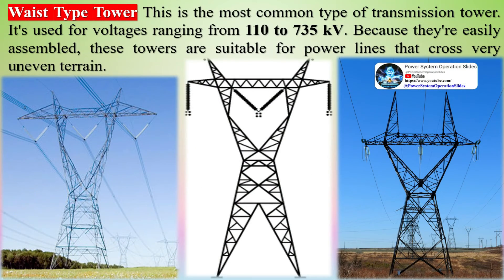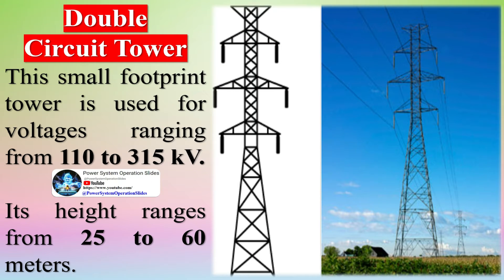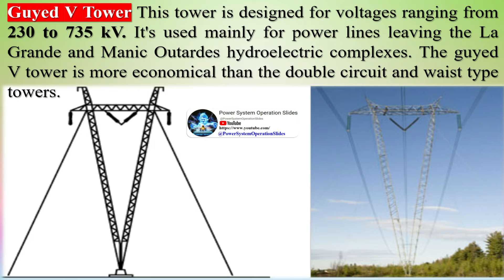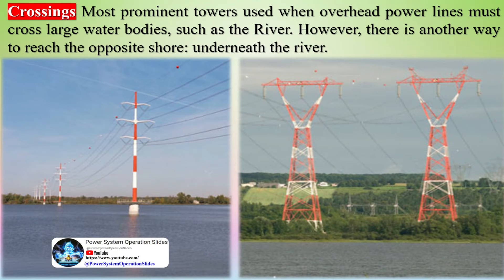The waist-type tower is the most common type of transmission tower, used for voltages ranging from 110 to 735 kV. Because they are easily assembled, these towers are suitable for power lines crossing very uneven terrain. The small footprint double-circuit tower is used for voltages from 110 to 315 kV. The Guyed V Tower is designed for voltages from 230 to 735 kV, used mainly for power lines leaving the La Grande and Manic-Outardes hydroelectric complexes, and is more economical than double-circuit and waist-type towers.